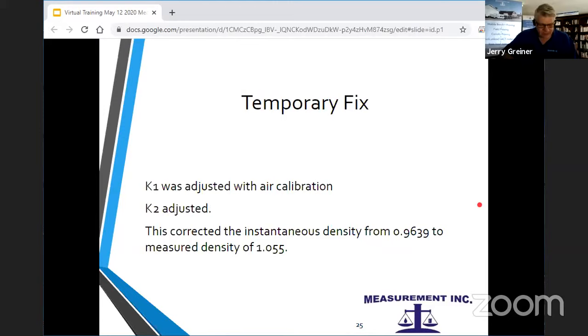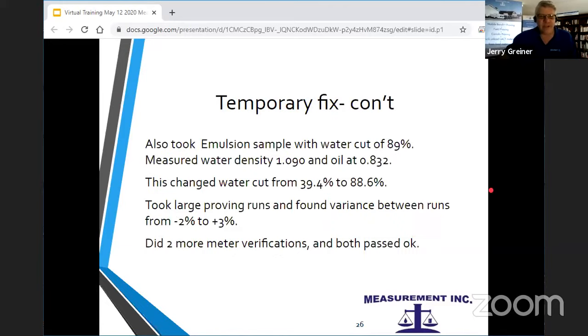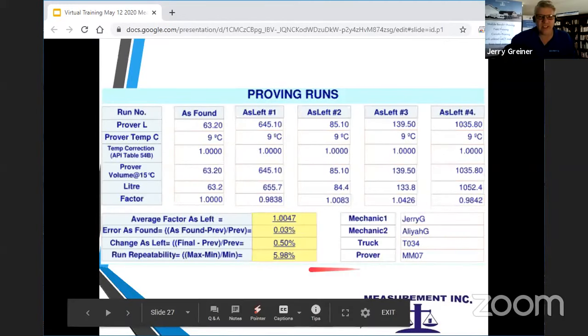We did a temporary fix just to see if we could make an adjustment and make it sort of work. We did that with a K1 with an air calibration, and K2 we adjusted till it got the correct density. It's not really right, but it's a troubleshooting temporary fix. Then we took the emulsion samples after the temporary fix and measured the water density and the oil density and everything. Once we temporarily fixed it, it was sort of close, but still a huge variance between runs. We did 2 more meter verifications after this temporary fix, and it didn't work.